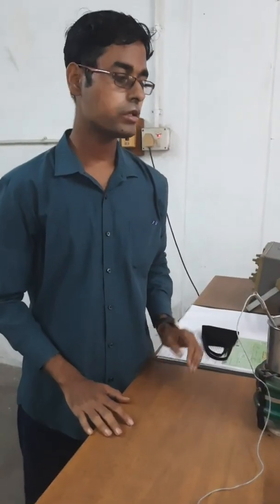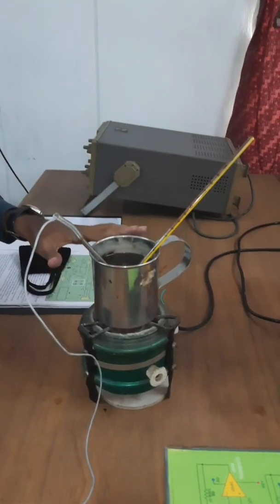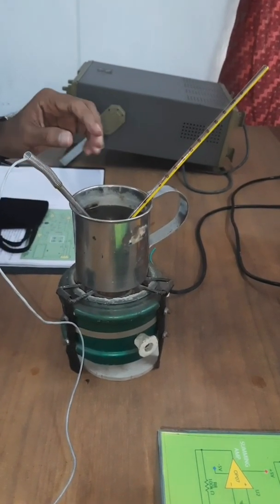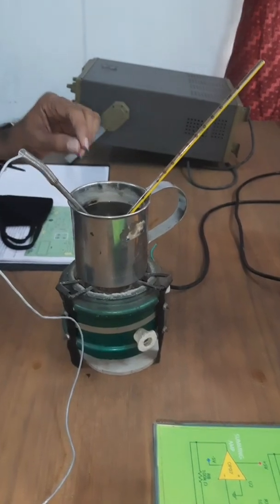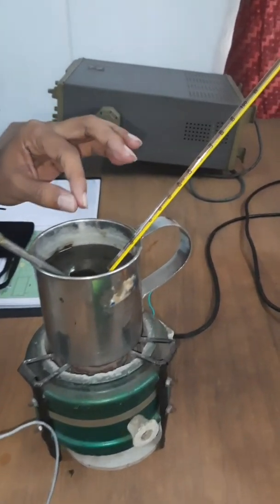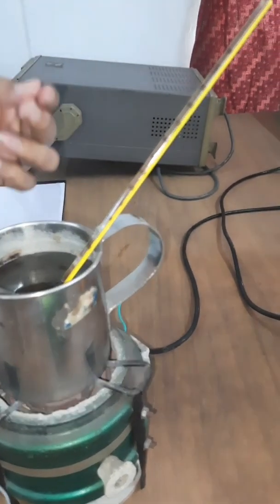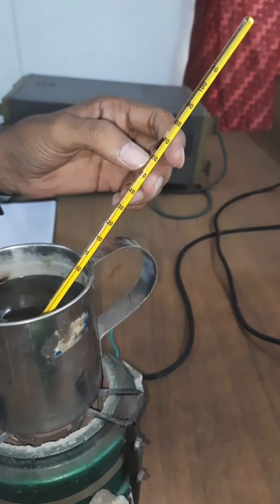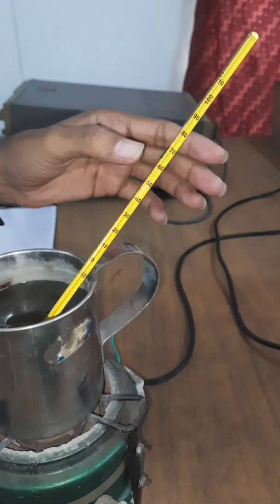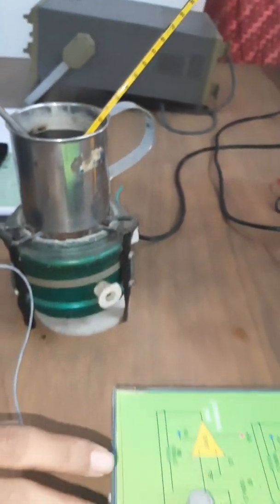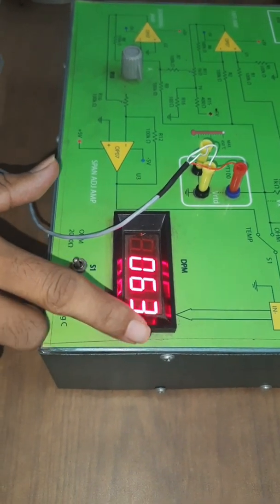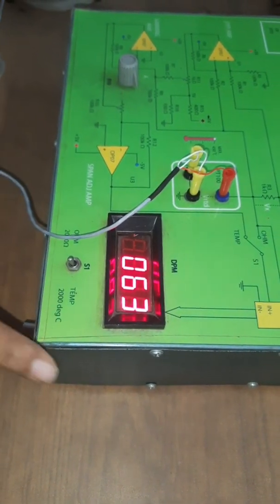Continuing further, we have cut off the supply to this heater. But you would remember from your thermodynamics course, that even if we cut off the power supply, due to thermal time constant, this process fluid will still heat a bit further. The temperature will slightly increase a bit more than 60, going up to around 62 degree centigrade. We have done the calibration with 60 degree in mind and you can find that corresponding to the 63 degree centigrade right now, this is also showing 63 degree centigrade.